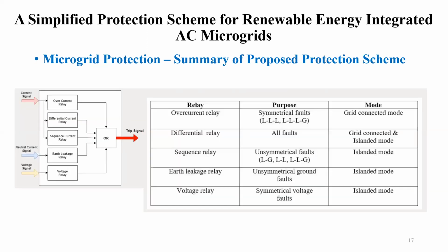So overall, this is a summary of in which mode we are using each relay and what is the purpose of each relay. So this is a summary of that. For example, the differential relay can be used for all faults, and it's used in both the grid connected and islanded mode of operation.